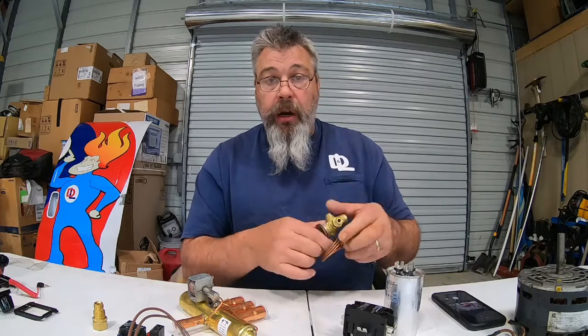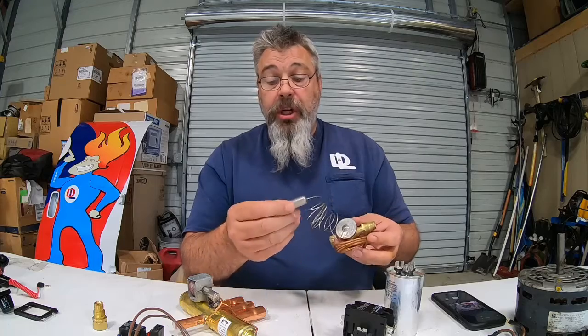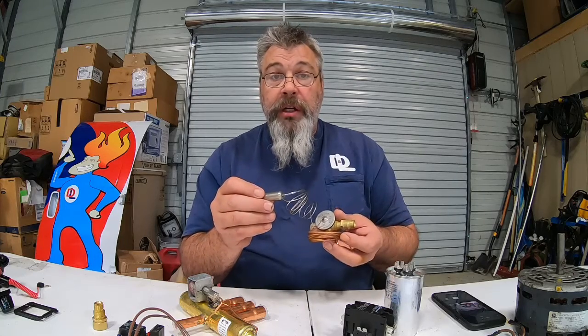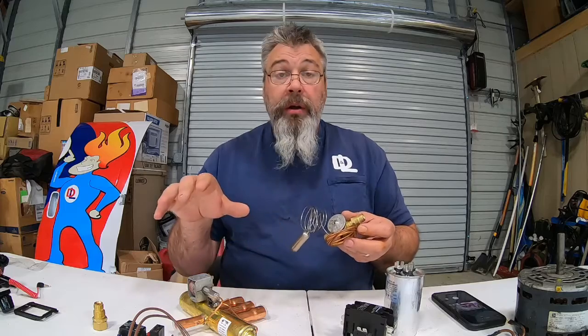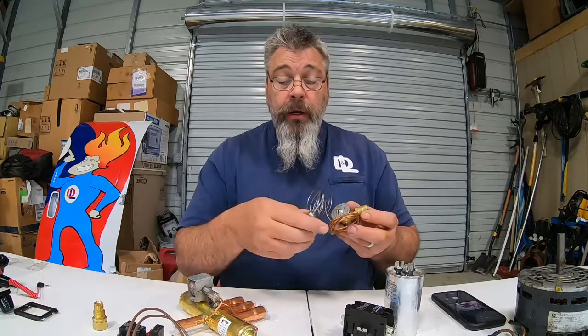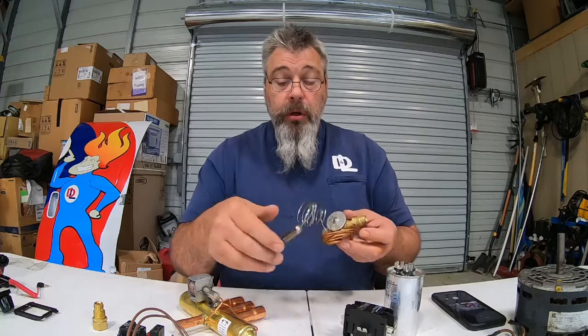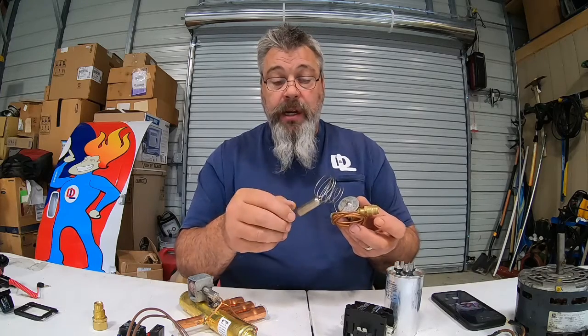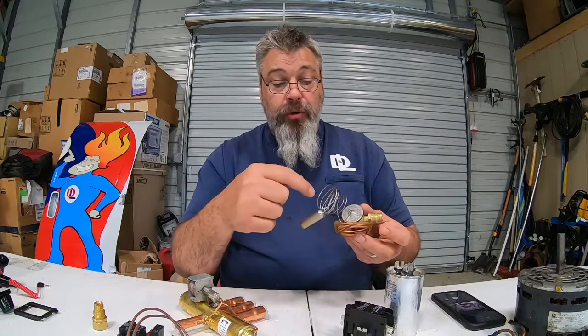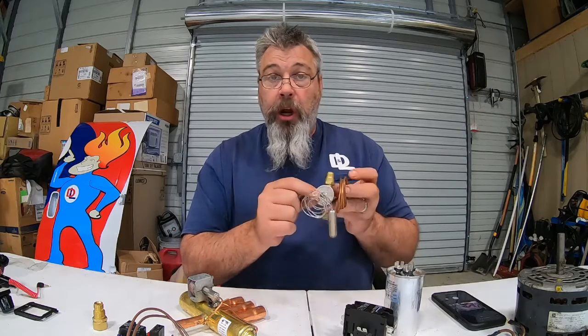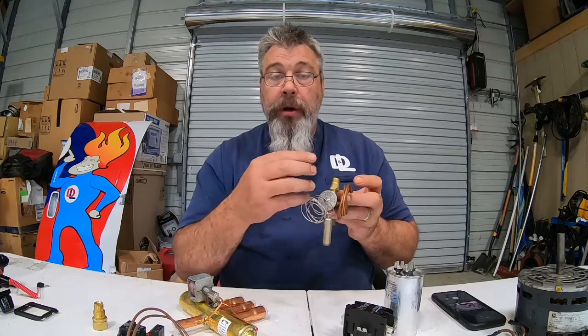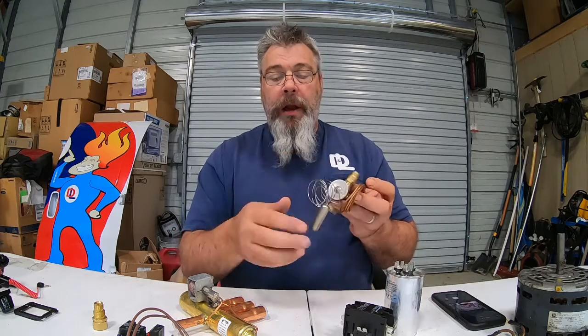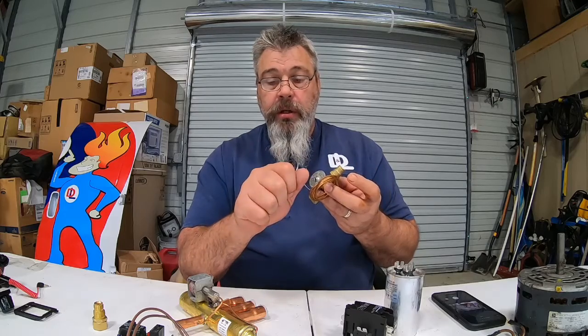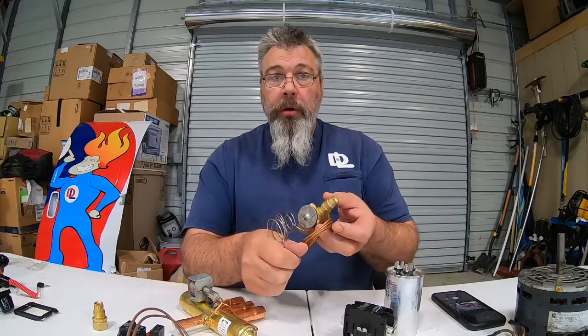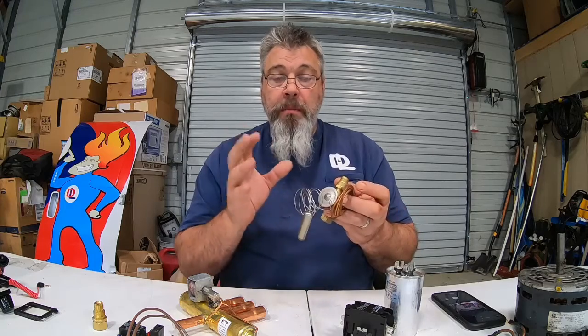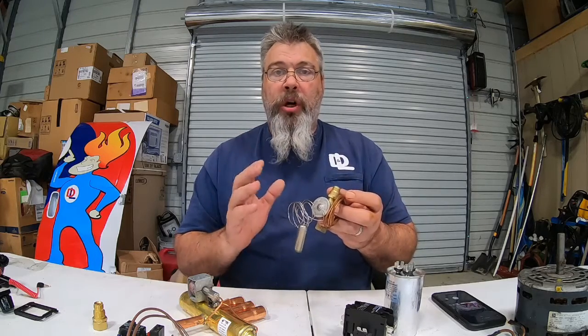There's a plunger inside here. There's a power head here. This goes to one of the lines on the condensing unit. This, similar to what the frost sensor did, measures temperature. This is pre-charged with a gas inside. As that heats up, that gas goes through this little tube to what they call the power head. That power head in turn opens and closes based on what it needs off of this. So if you heat this up, it's going to open more. If you cool it down, it's going to close more. It's a metering device. We're going to meter the amount of refrigerant going in.